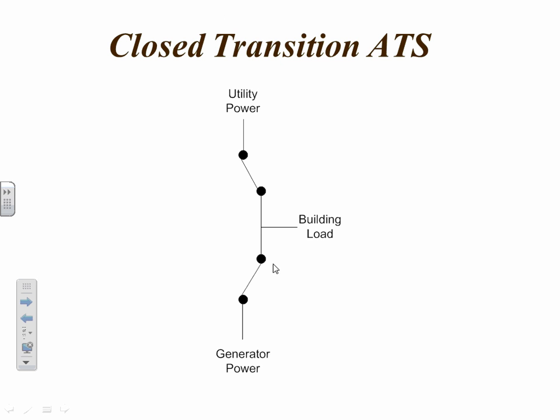Again, it has two pivot points. What I've shown here in this sketch is that 100 milliseconds of time when the load is closed to both sources. So utility is there, generator is here. Both sources are closed. But they figure for 100 milliseconds you can't hurt too much, and then it opens. So we're going over to generator now. This is going to open in 100 milliseconds, so only the generator will be feeding power to the building load. That's the concept.